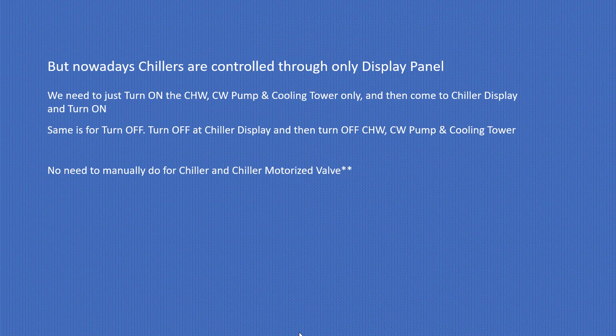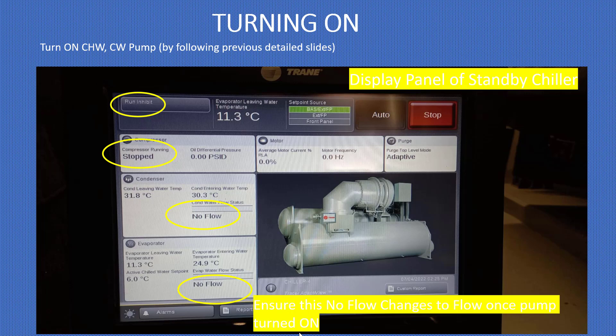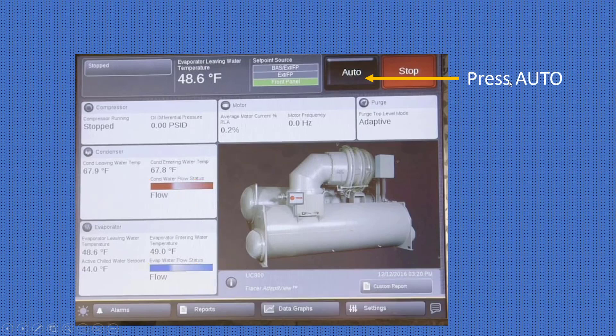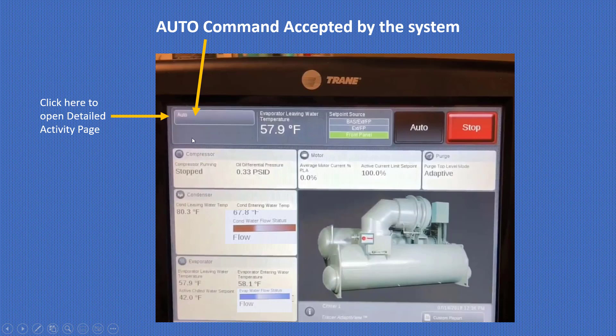Nowadays chillers are controlled through the display panel only. You need to turn on the chilled water pump, condenser water pump, and cooling tower, then come to the chiller display and turn it on. Same for turn off: turn off at the chiller display first, then turn off condenser water, chilled water, and cooling tower. Check based on your panel construction. When turning on, ensure the 'no flow' changes to 'flow' once the pump turns on, then press auto and observe all parameters.